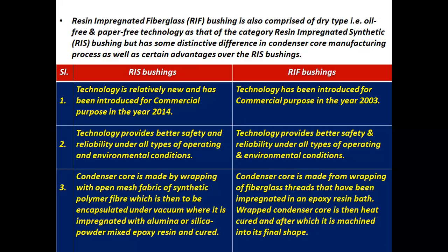The wrapped condenser core is then heat cured, after which it is machined into its final shape. The only difference is that here it is used only in an epoxy resin bath, but in the case of RIS bushing, it is alumina or silica powder mixed epoxy resin and cured.